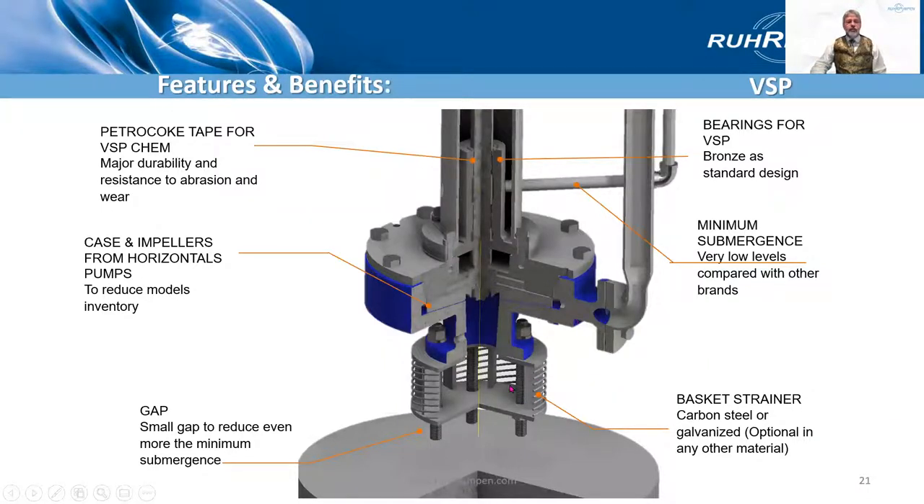Now we're looking at the bottom end of the pump. We see the basket strainer, which is optional — you wouldn't need it in clean pumpage but you would always use it in dirty pumpage. It's designed not to keep out polythene bags, but to keep out bolts and large debris. The hydraulics are from the chemical process pumps, so they're identical to the horizontal ANSI pumps — we just install them into this type of pump. The bearing here is Petrocoke tape for the VSP Chem, and it's bronze in the standard cast iron pump.